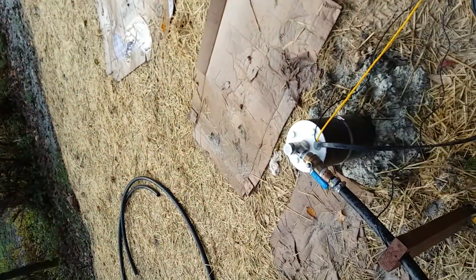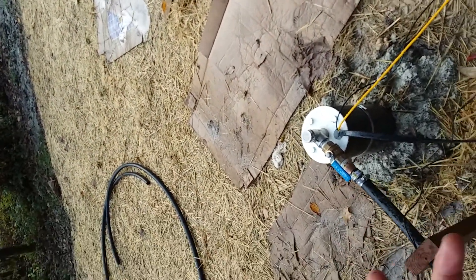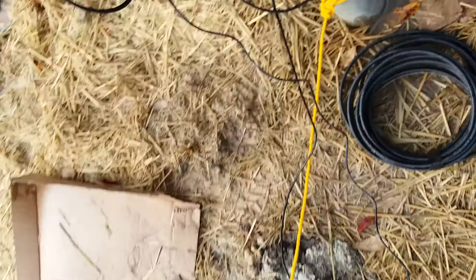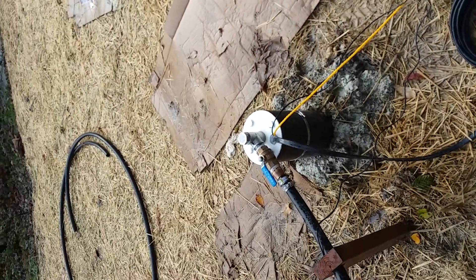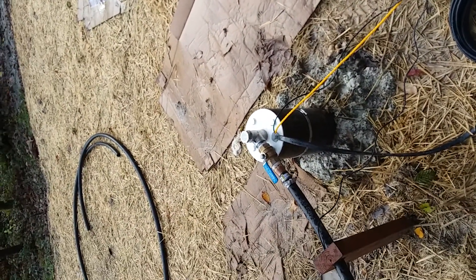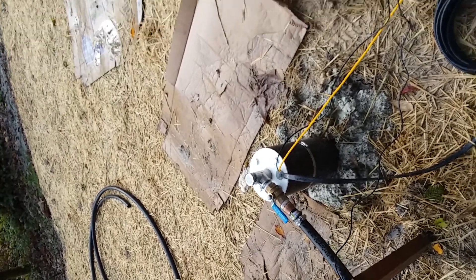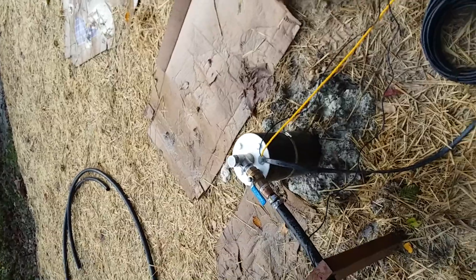I don't anticipate that sensor ever triggering because we have 48 gallons per minute and this pump isn't going to keep up with that at this depth. We lowered the pump, wires, and safety rope down 68 feet — which is 20 feet below our static water level — and a couple feet above the pump is that well low sensor.